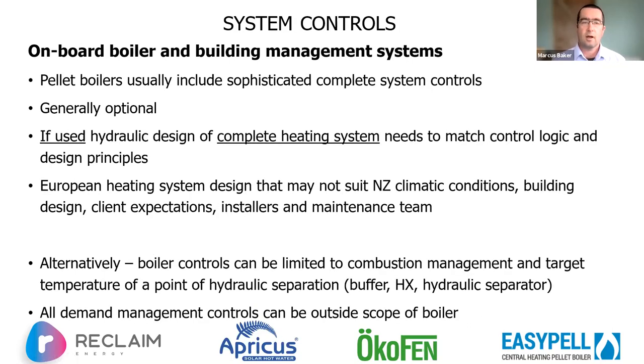Something about controls. Pellet boilers often have really sophisticated controls, but in my opinion, it should be optional whether or not they're doing more than just managing the combustion on the boiler. The Okofen boilers, for example, and plenty of the other ones will do all sorts of highfalutin system design, so complete system management. But, and I really emphasize, but, the hydraulic design would then have to match that control logic and design principle of the boiler. It's really important to understand.